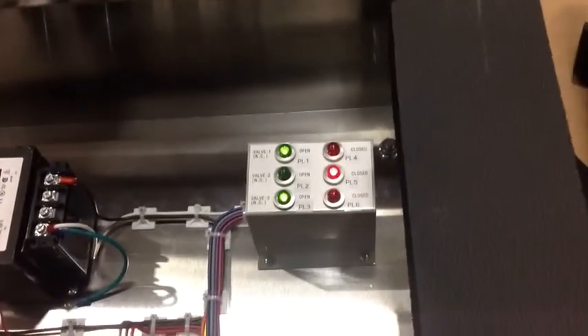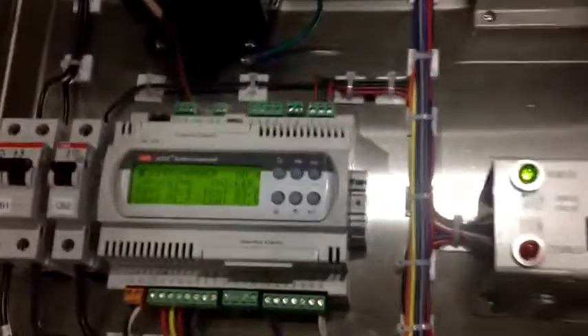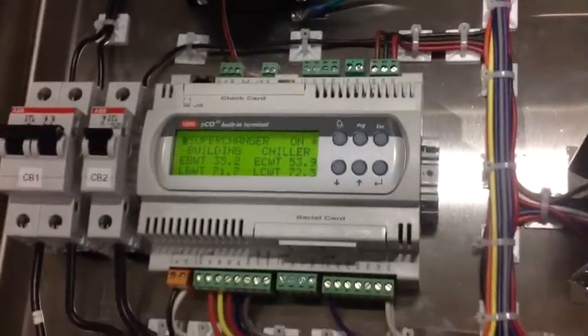to see the indicator lights. So again, 2 isolation valves and a bypass valve all go in the building comfort cooling loop side of the heat exchanger. And now we're looking inside the control panel, and you see the green lights indicating that the isolation valves are open, and that PL5 there is the bypass valve that's closed, and that's because the temp sensors are in the cold water. You can now see the 35-degree entering water.